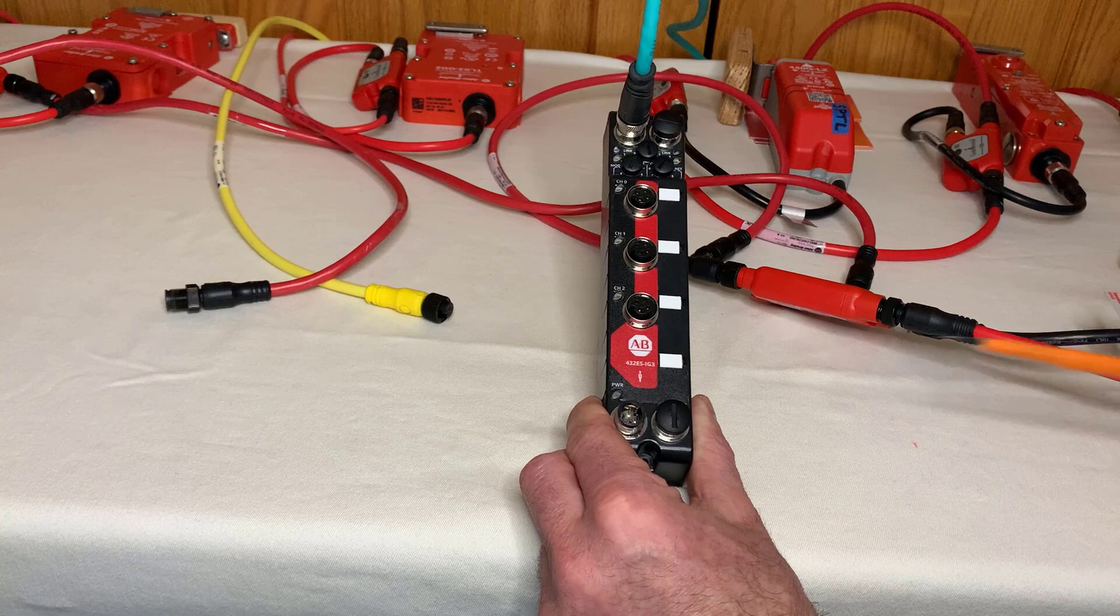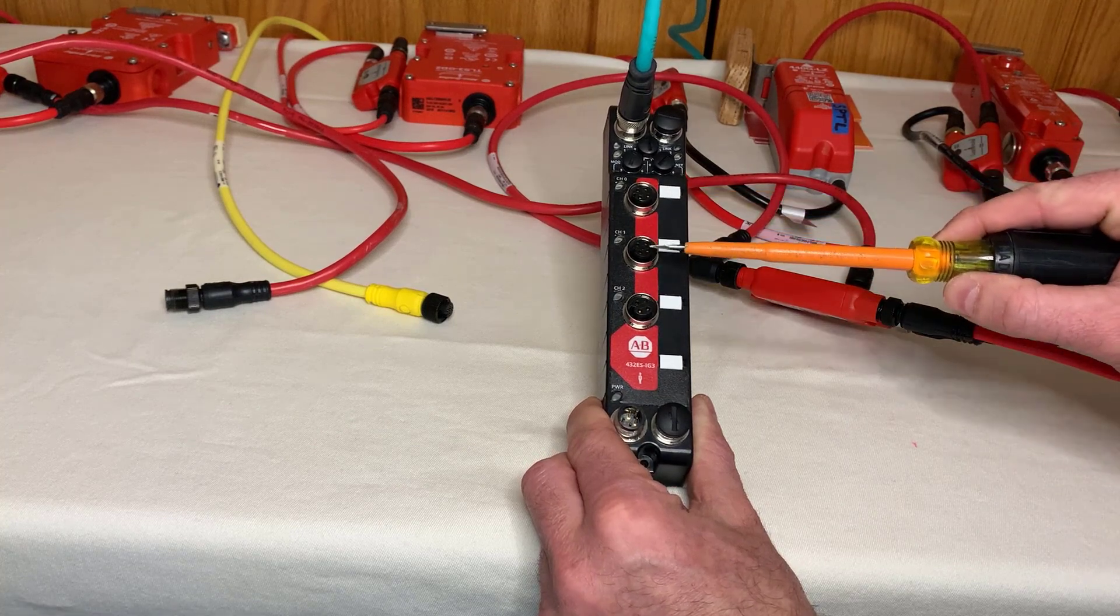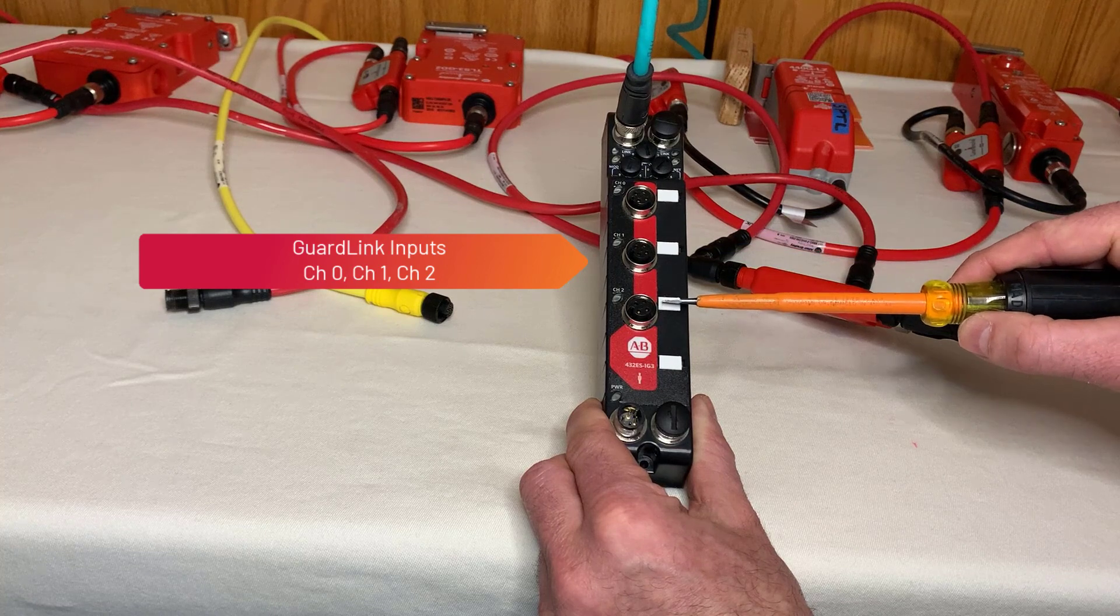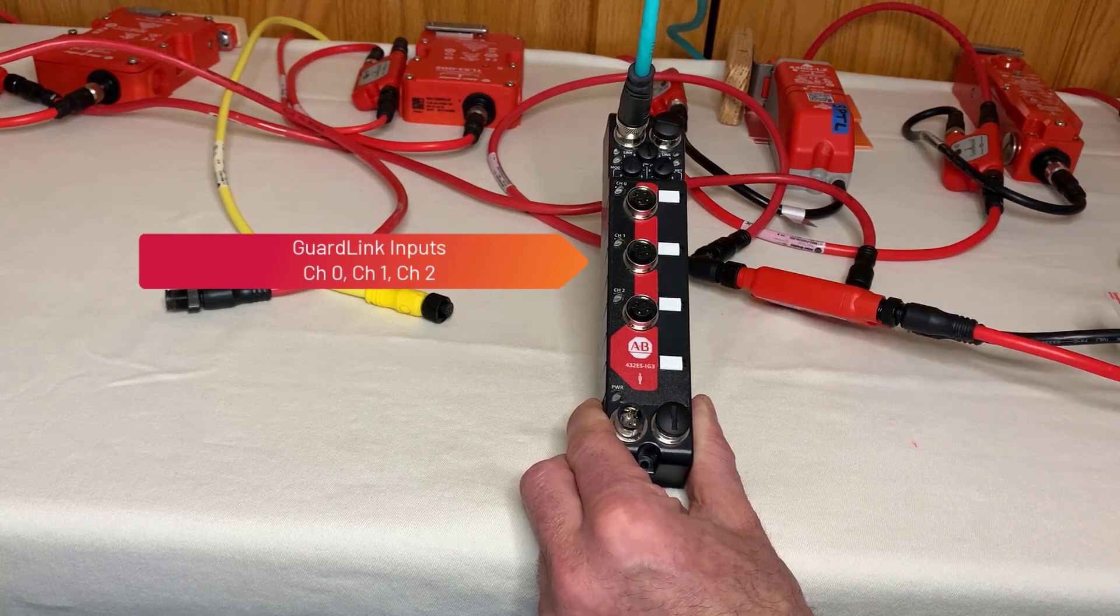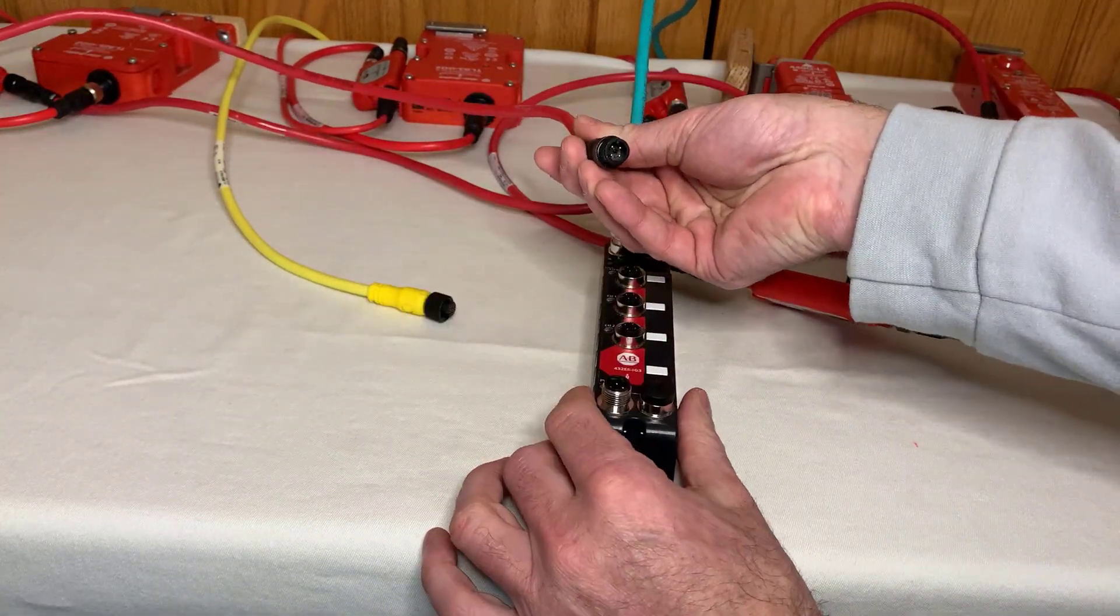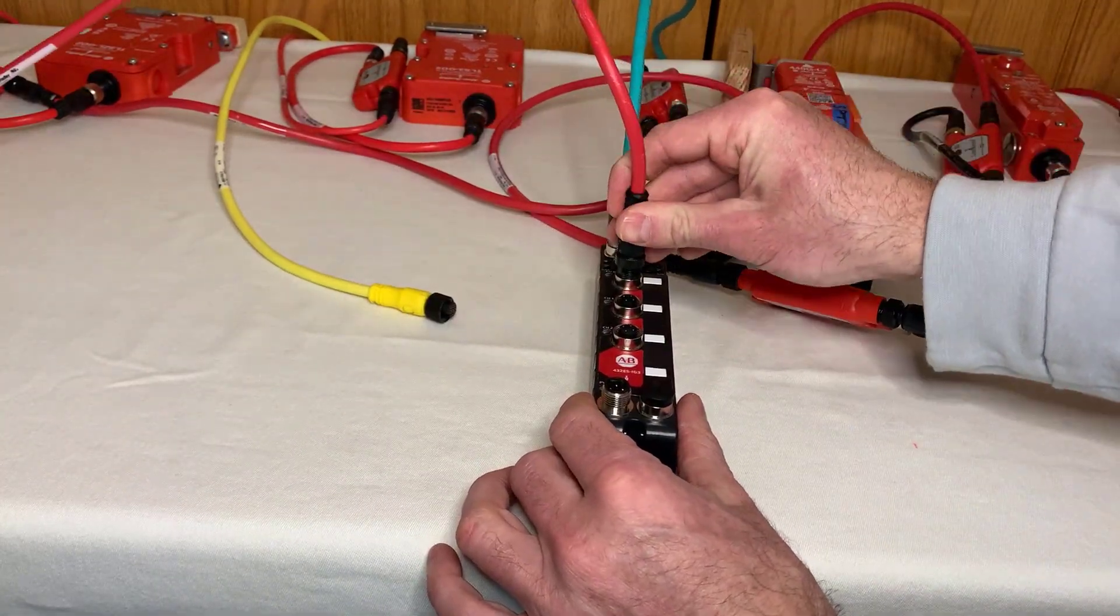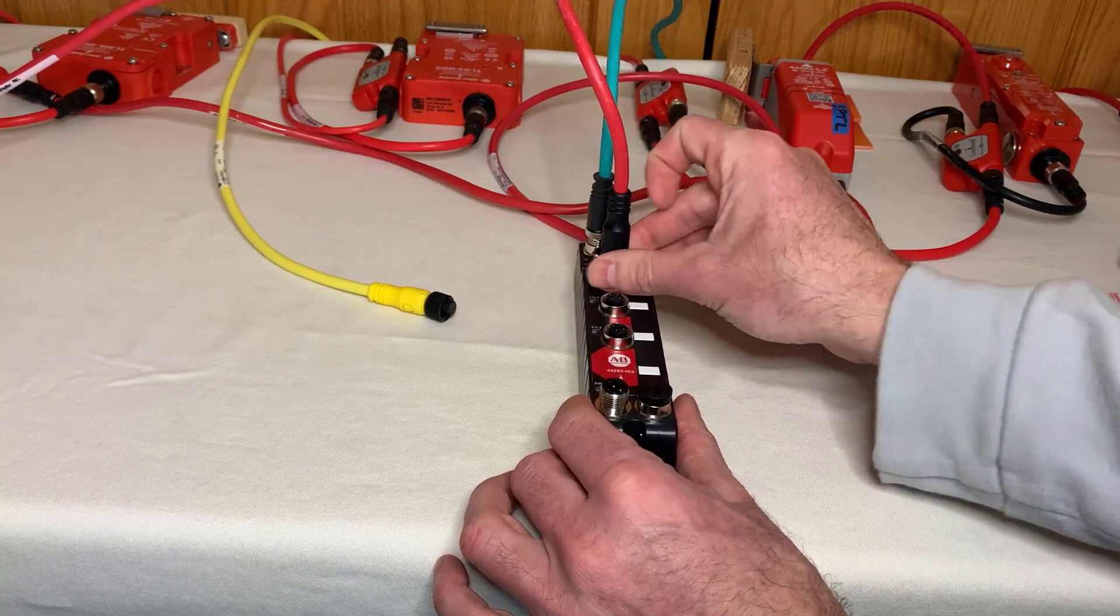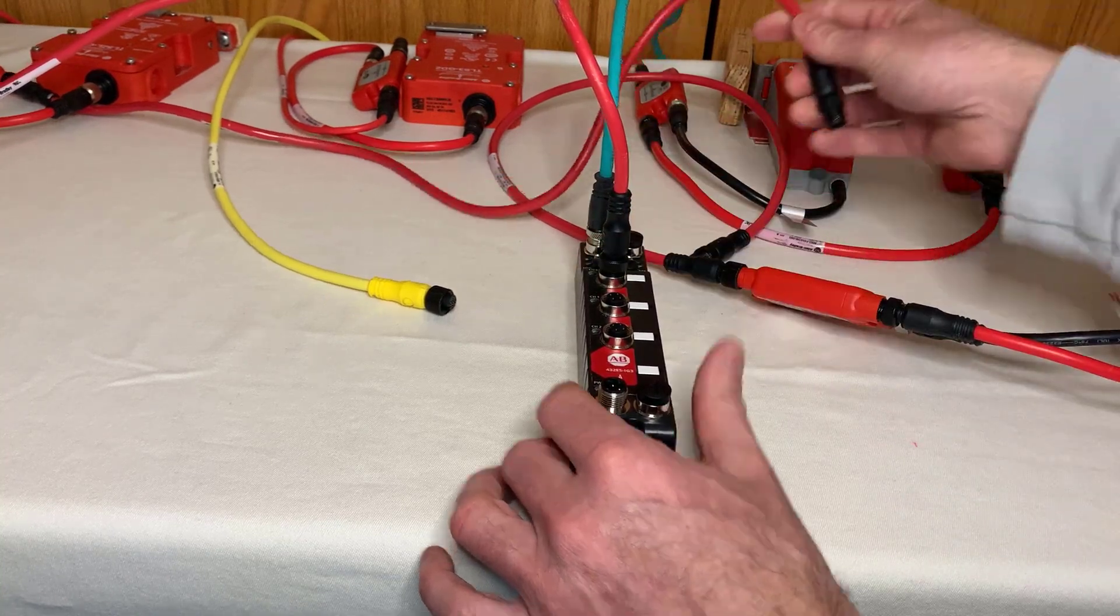The three 4-pin M12 plugs are labeled Channel 0, Channel 1, and Channel 2. These are the three GuardLink safety inputs. A 4-pin M12 trunk cable is used to connect the GuardLink interface to the first GuardLink tap of each channel. Each GuardLink channel is capable of monitoring 32 devices.